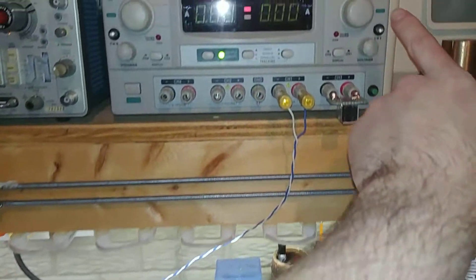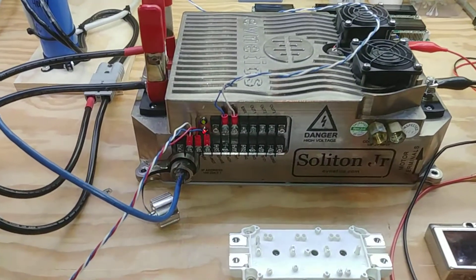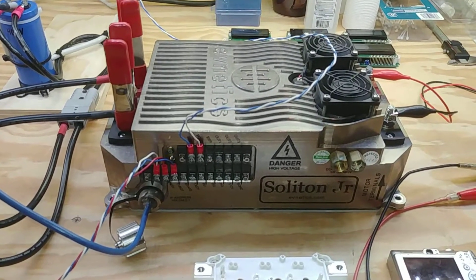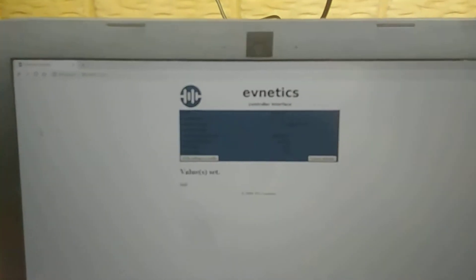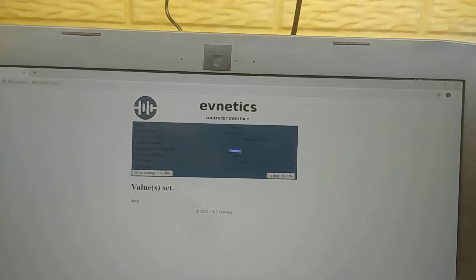We go ahead and power up 12 volts to the drive, let it boot up, and do its little pre-charge. It should be ready to go. Let's see if the website comes up — there it goes.